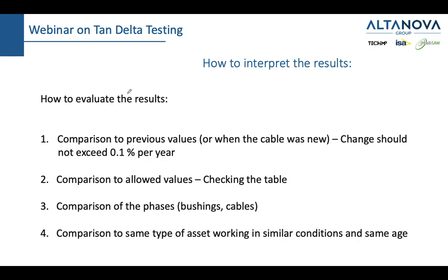And one thing which Mr. Simone Meneghin mentioned, because we did have that same question, in the morning session is you need to understand what the value of this negative tan delta is. Are we talking about -7% or -0.01%? Because if you have -7 or 3 or 1.5%, probably you have issues with the execution of the measurement. You are not measuring correctly. But if you have -0.01, in that case, you are probably dealing with a very good insulation, and the accuracy of the measurement is maybe not that great. So while measuring the current and calculating tan delta, there might have been some errors which happen while calculating tan delta.